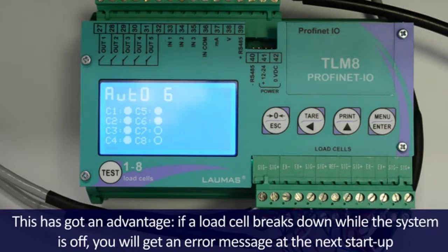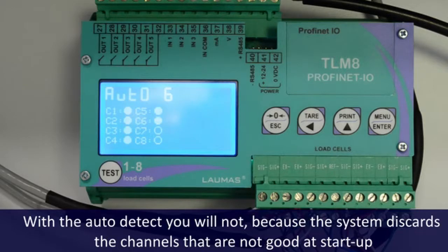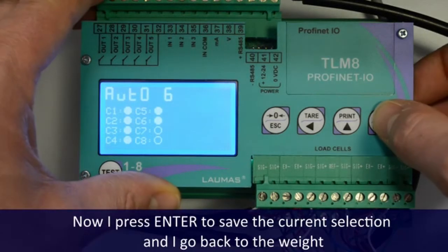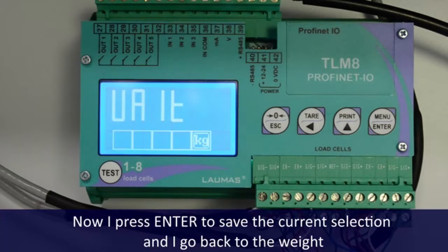This has got an advantage. If a load cell breaks down while the system is off, you will get an error message at the next startup. With the auto detect, you will not, because the system discards the channels that are not good at startup. So I press enter to save the current selection, and I go back to the weight.